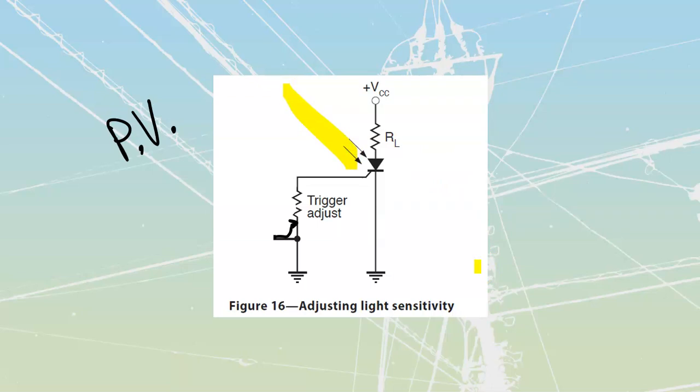LASCRs themselves are going to be control components. They're not going to be bulk current carrying components. It's not like you're going to grab one of these and think, hey, it'd be cool to have a heater that I could turn on and off with a flashlight. You're not going to just stick a single LASCR inside there, because in most cases they are limited to small values, an amp or under. Sometimes you can go higher. They do go in wattages almost up to 0.5 kilowatt, anywhere between the 300 to 500 range is where we'll commonly see them, but it's not going to be large amounts.